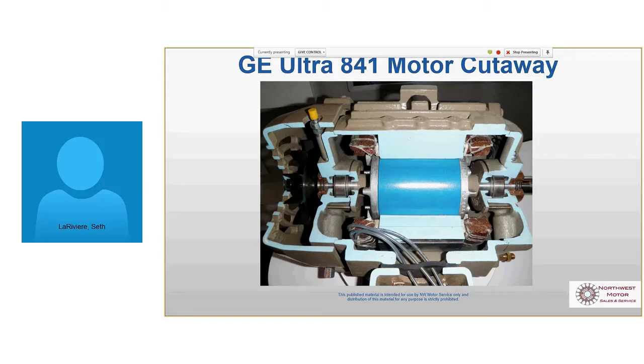These have 4 cast-in lifting lugs. Each one will support 4 times the weight of the motor. So your motor and your driven equipment could come with it. You can pull your pump and your motor not disconnected as long as it's within those weight limits of 4 to 1. So you've got one here. You would have one here. It's been removed. And then there's also one on the bottom of the motor here and here. So if the motor's mounted vertically, you can still get your hook into those holes.